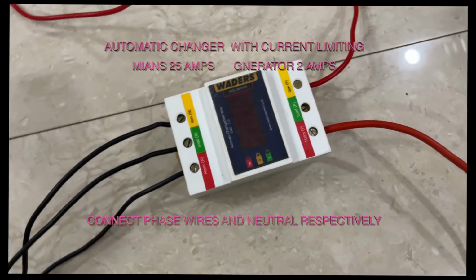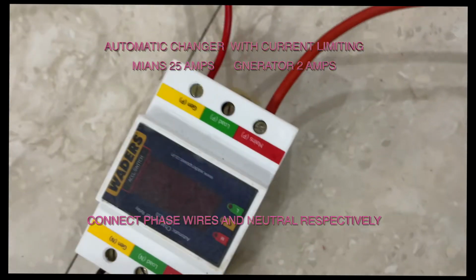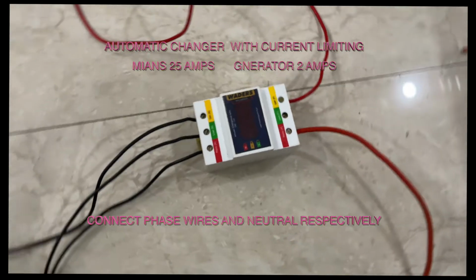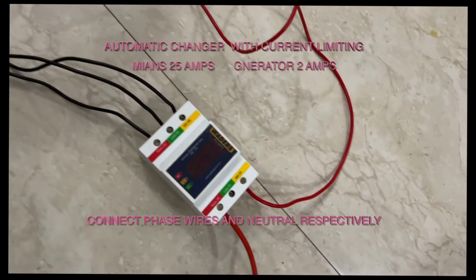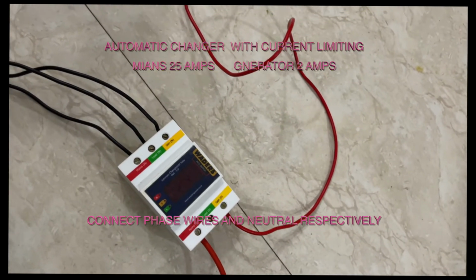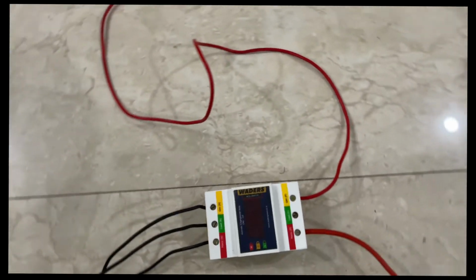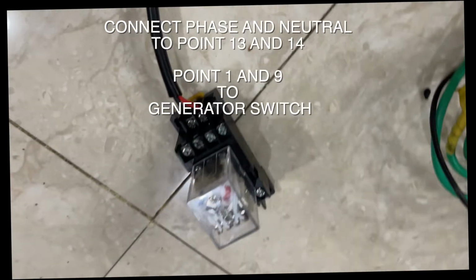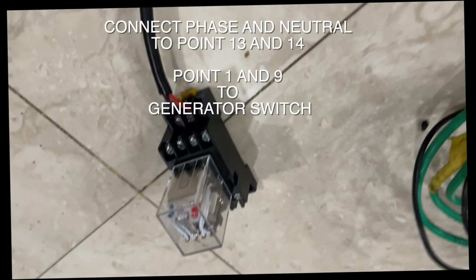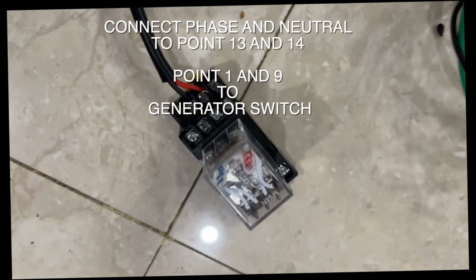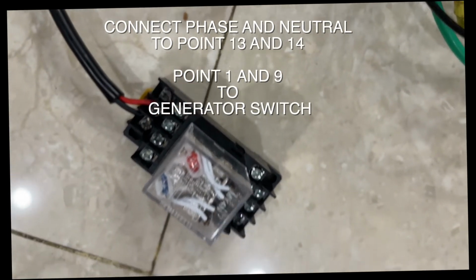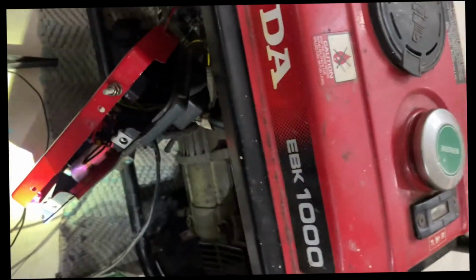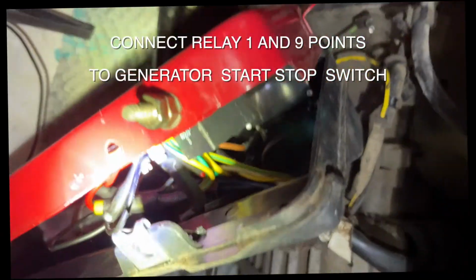This automatic changeover switch is clearly marked where to connect the main line, where to connect the generator line, and where to connect the load, for which you need to connect the phase in the phase lines and neutral in the neutral lines. Now you can connect a 14 pin relay, and mostly 13 and 14 are the points for power supply, and you can use any of the other contacts, 1 and 9, for the generator connection.